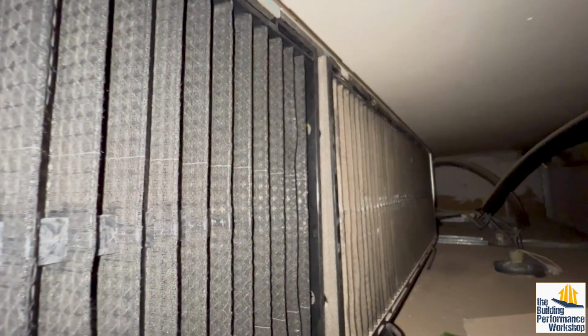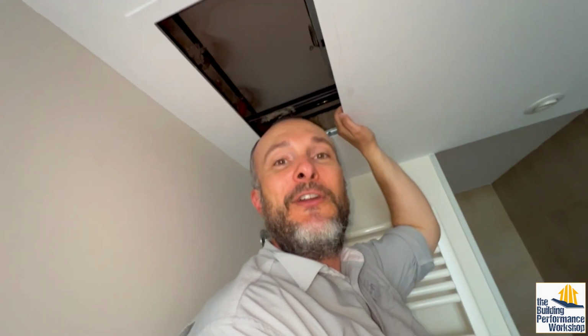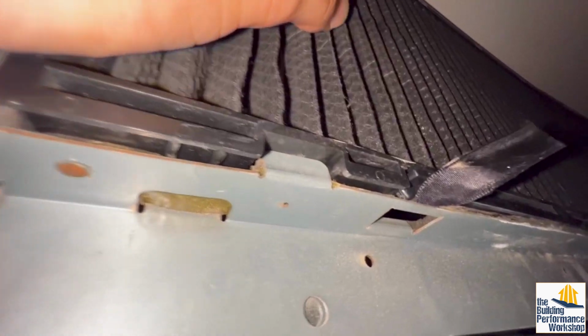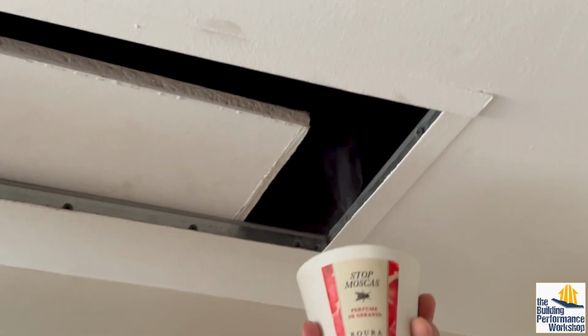This one I have just cleaned. This one is uncleaned, and it's because it's so far away from me that I'm nervous to even reach up there. You can see through the filter, and this filter is like a MERV 3, MERV 6 tops, but highly doubtful. Also, when I found it, it was not seated correctly. So I have since fixed that, and now it's squared off all the way down. And you can see that the ceiling is depressurized by this smoke getting pulled up into it.